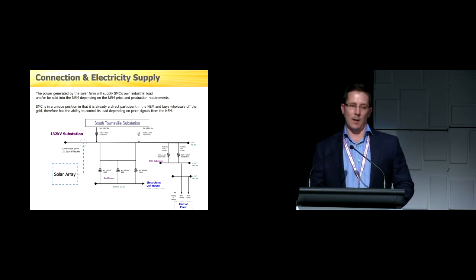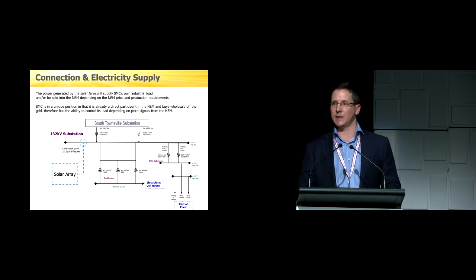So how the solar farm will be connected - the line diagram shows the existing substation at the refinery. The solar project will connect to that existing substation at the 33 kV bus, and during normal operation, 95-98% of the time, that solar generation will go to the refinery and be consumed by our normal operations. The advantage we have is if the power price is high, we can choose to send it back the other way into the grid, since we're connected directly to the transmission network from that substation. So it's a big advantage for the refinery, having an existing substation and an existing connection agreement.